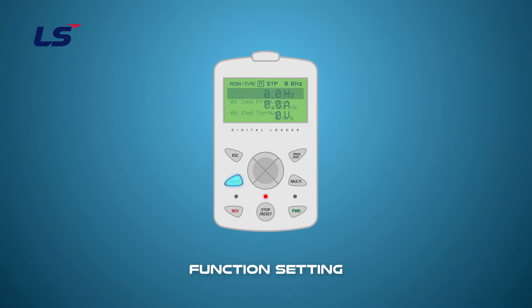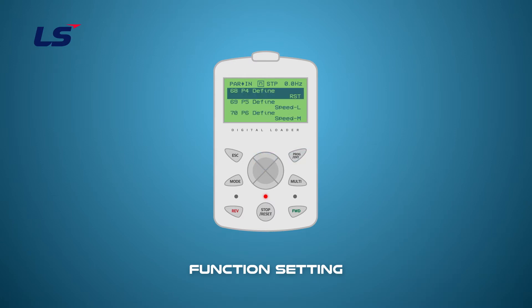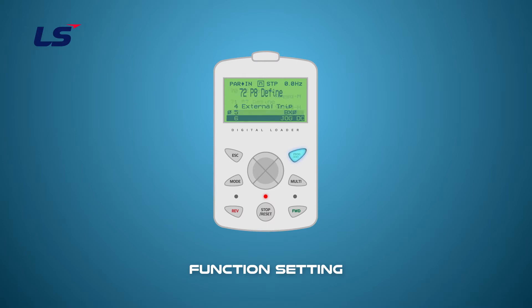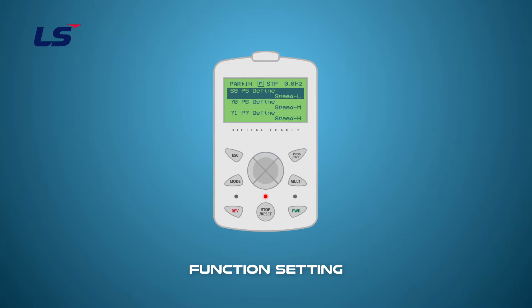Defining the multi-function terminal is a function that is performed when a signal is entered into the terminal. This function can be set at IN65 to IN72 of the IN group. The terminals P5, P6, and P7 are set to Speed-L, Speed-M, and Speed-H by default. In this video, the multi-function terminals for multi-step acceleration-deceleration are set as XCEL-L and XCEL-M on P4 and P8.